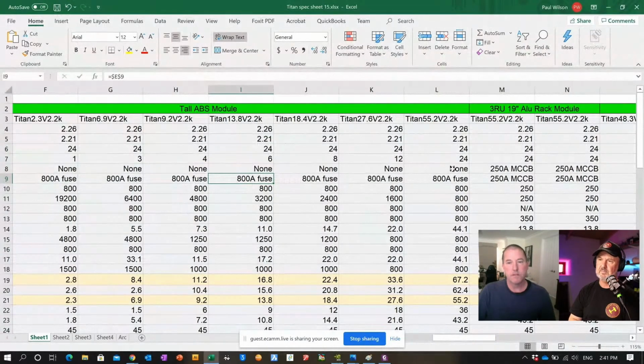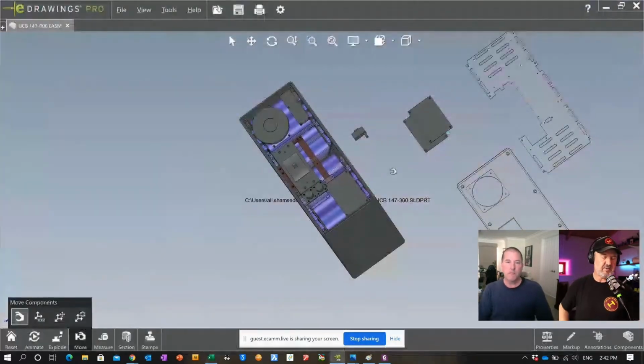Provided you've constrained the voltage limits on your inverter, for example in the lower voltage range, making sure you didn't charge past 65 volts, which is pretty easy to do, and didn't go under 35 volts. Even having said that, the UCBs are pretty tolerant to being discharged completely. They don't fail from over discharge, so you can discharge them to zero multiple times and they'll come back again. So you don't have to have comms from your inverter, but having comms on the larger one gives us a lot of extra features, like letting us offer a longer warranty because we know it's being treated properly.